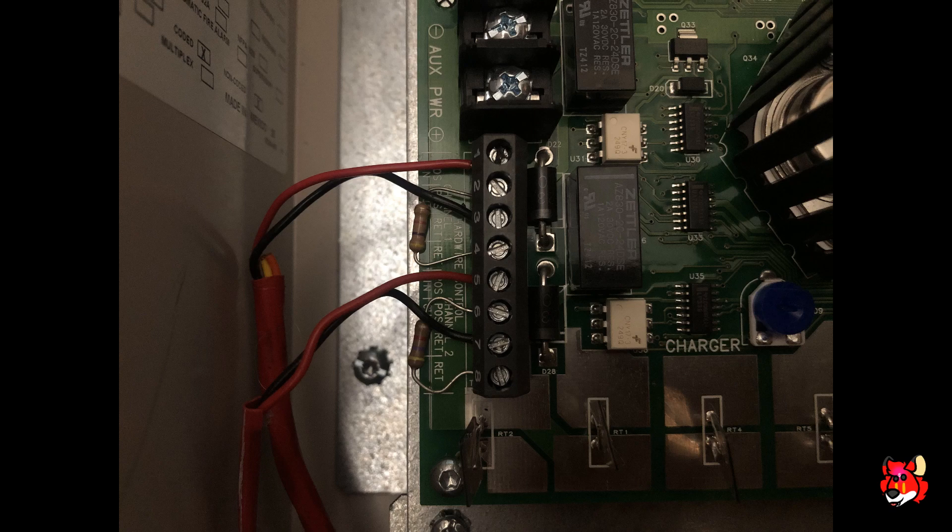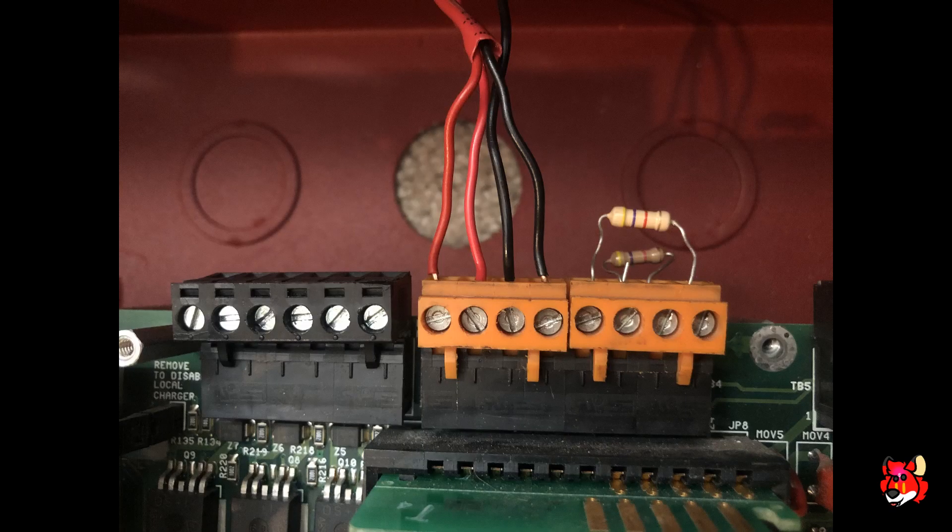Here's how I have it wired on my Fire-Lite MS-9600 — the same applies to any other control panel. I'm using NAC 1 for the horns and NAC 3 for the strobes. NAC 3 is set for non-silenceable and goes to channel one, the strobe input on the power supply. NAC 1 goes to channel two on the power supply. If you were not using audible silence, you would only use one circuit.